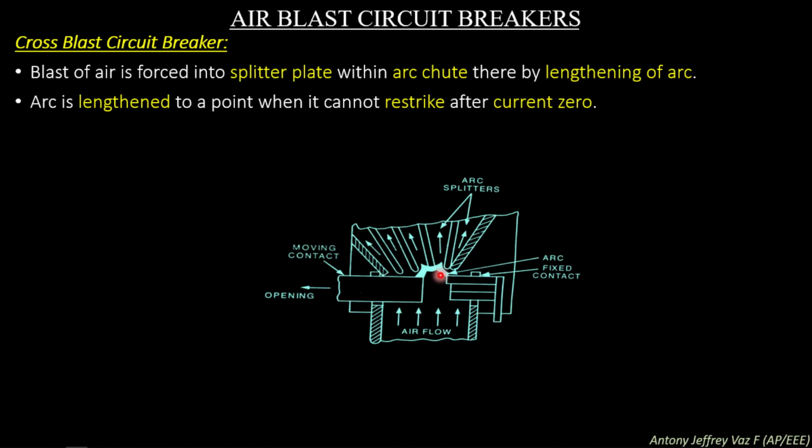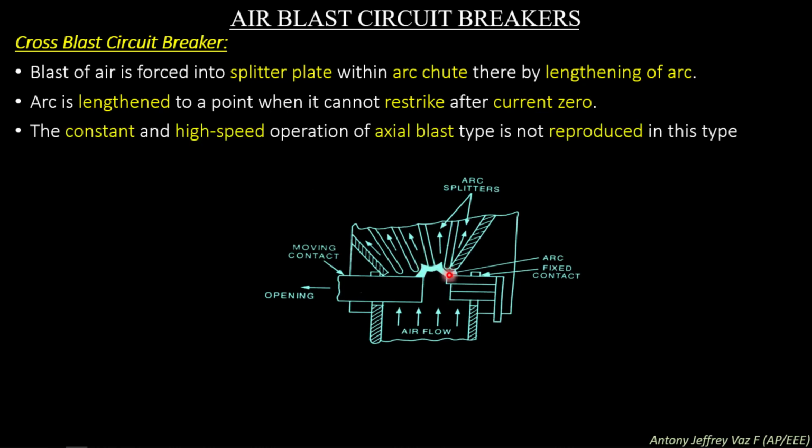Since the arc is lengthened, the diameter of the arc gets very much reduced. Since fresh dielectric medium of new air is flown perpendicular to the arc, at once the diameter of the arc is reduced and lengthening of the arc also occurs. At the same time the arc is also cooled. So during this time the arc gets extinguished very easily.